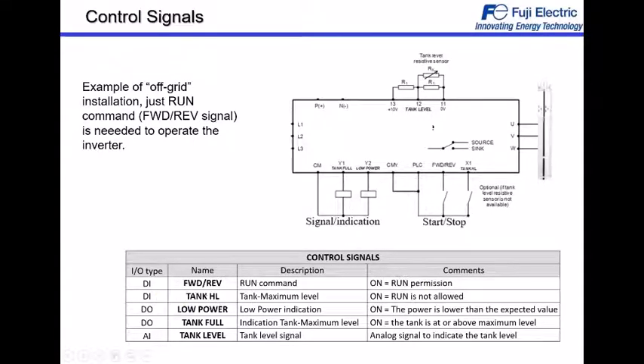A digital input, tank level, high level. Tank is at the maximum level. So when it's on, this input means run is not allowed. There is a digital output, low power indication. When this signal is on, it means the power is lower than the expected value. This means the power coming from the solar panels is not enough to run the pump. Another digital output is tank full. In this case, it is an on/off indication of the tank maximum level, storage at the maximum level. So if it's on, it means the tank is at or above the maximum level.